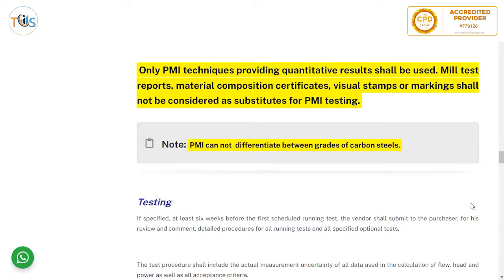Mill test reports, material composition certificates, visual stamping, or marking shall not be considered as substitutes for PMI testing. Conversely, PMI cannot substitute for mill test reports as they serve different purposes. PMI confirms that the right material is used, while mill test reports certify material with more accurate information including alloying composition, heat number, and batch number.